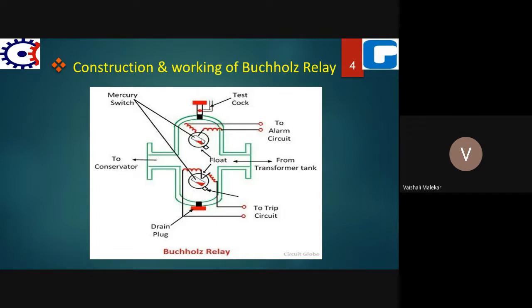In case of a minor fault, the float at the bottom of the chamber remains unaffected. If a minor fault is there, the lower side float will not get affected, because the gases produced will not be sufficient to operate it. Only the top side float gets affected, but the bottom side float remains as it is.